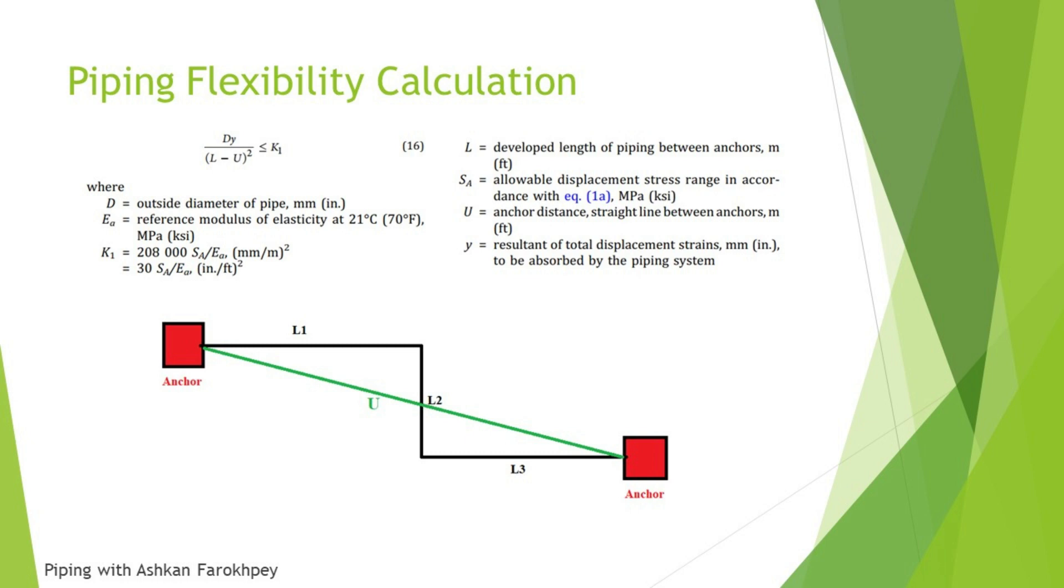In the next page you can see I have drawn a shape with two anchor points in red at the two sides of the shape and a piping system which is drawn in black. L1, L2, and L3 is the developed length of the piping system and U, which is the direct or straight line between the two anchors. Whenever you have a system or a piping system like this, you can use this formula for calculating the flexibility of your system.